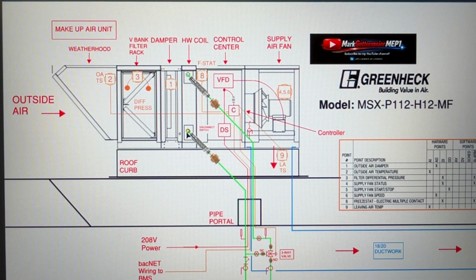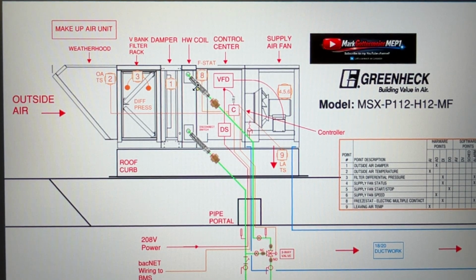Then we have our hot water coil that allows our hot water loop to pass through the coil and treat that air coming in. Then we have our control center, which comes with a disconnect switch and a VFD and a controller integral to it. And then we also have our supply air fan chamber here that draws the outside air in and pushes it down to the ductwork to serve the space.